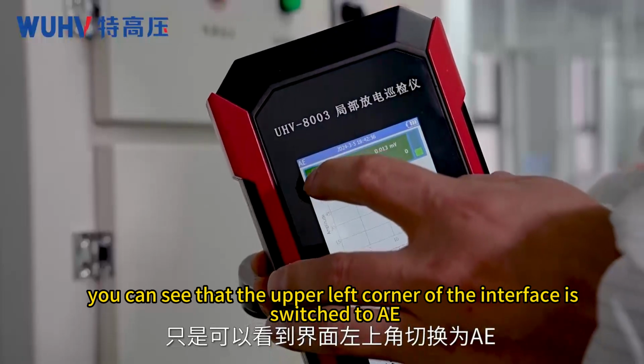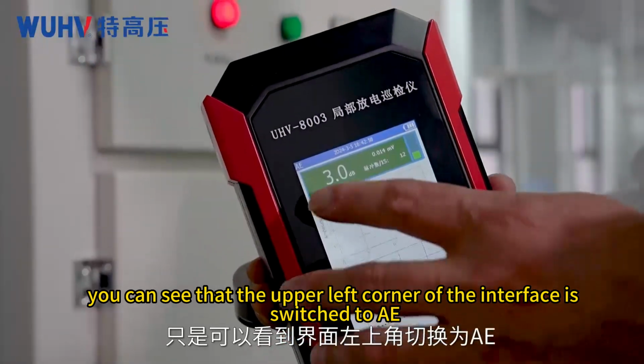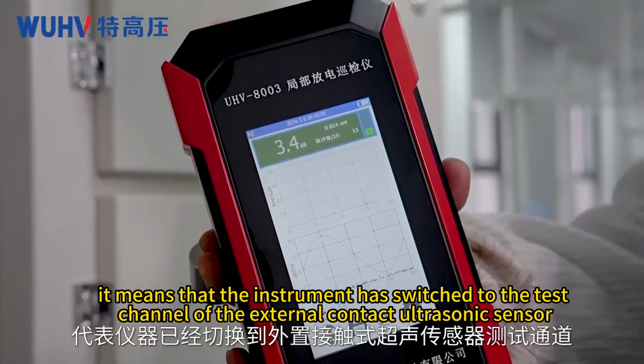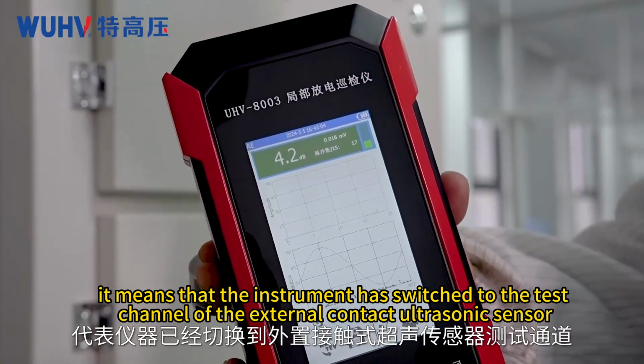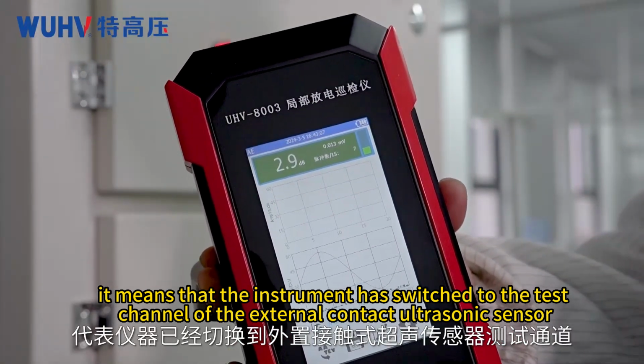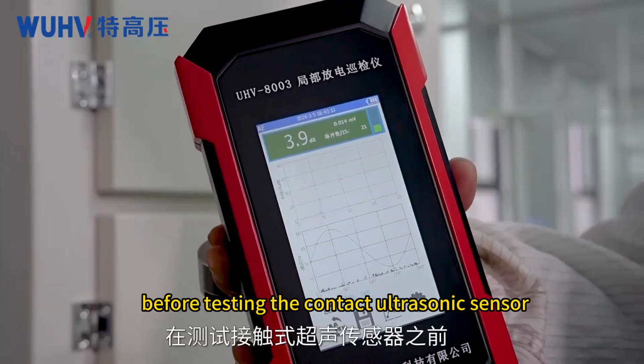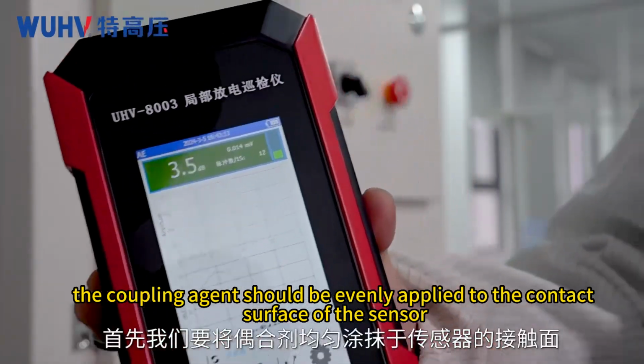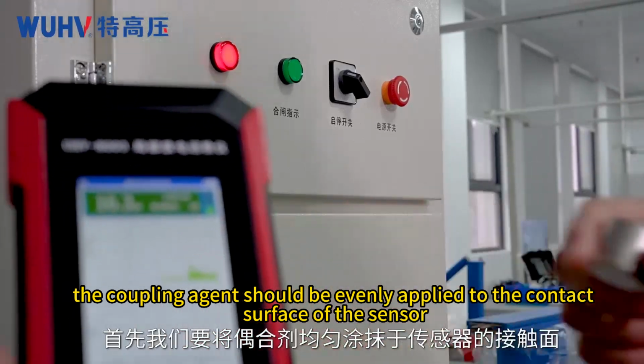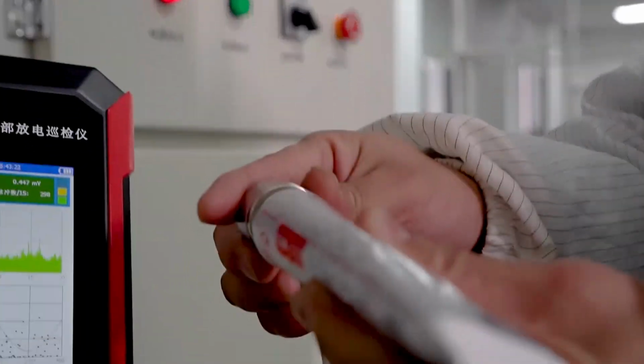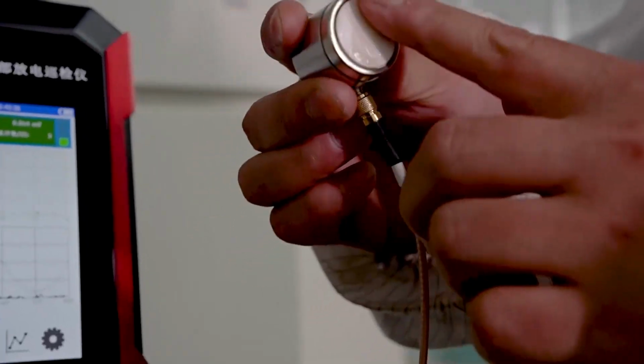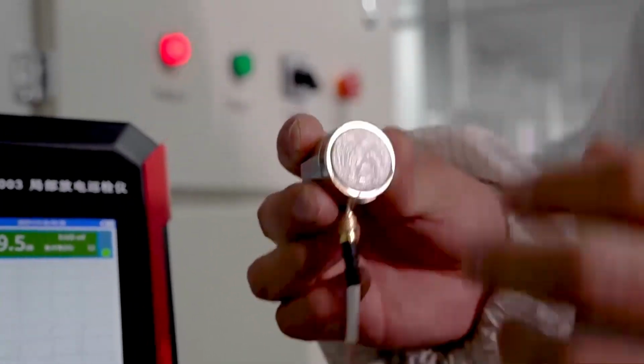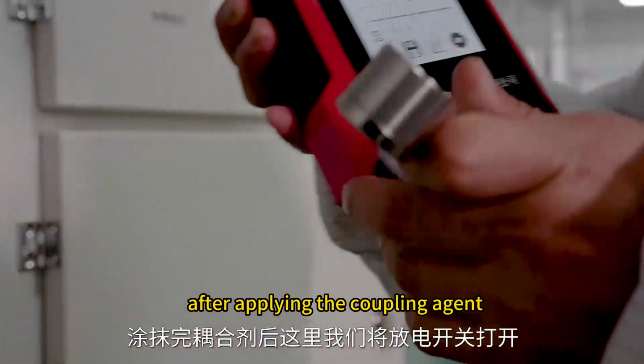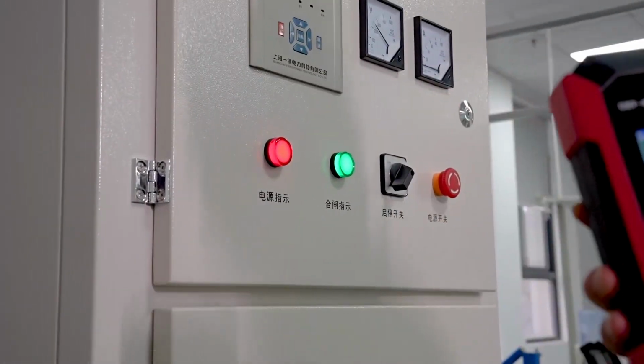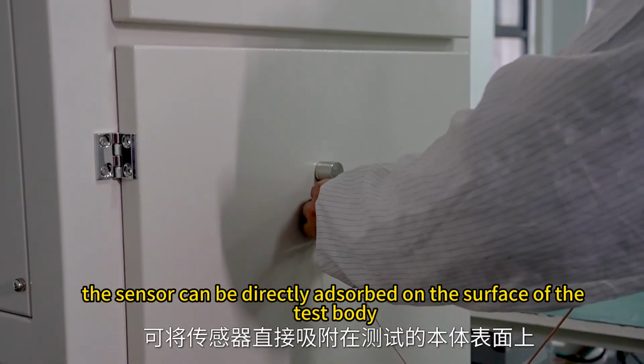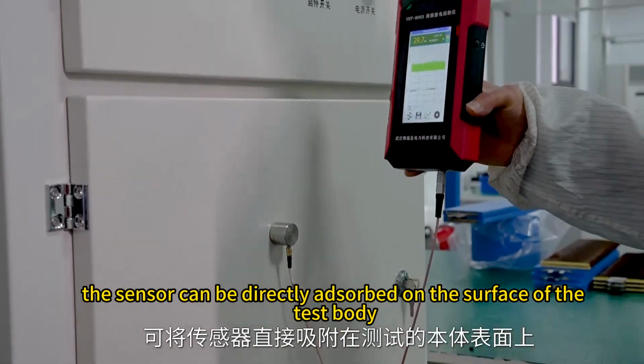You can see that the upper left corner of the interface is switched to AE. It means that the instrument has switched to the test channel of the external contact ultrasonic sensor. Before testing the contact ultrasonic sensor, the coupling agent should be evenly applied to the contact surface of the sensor. After applying the coupling agent, turn on the discharge switch. The sensor can be directly adsorbed on the surface of the test body.